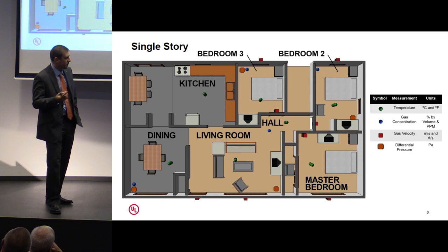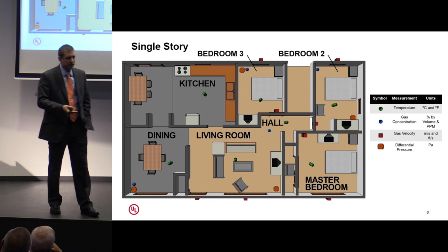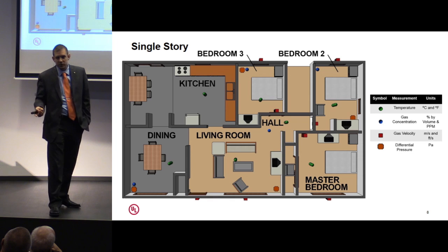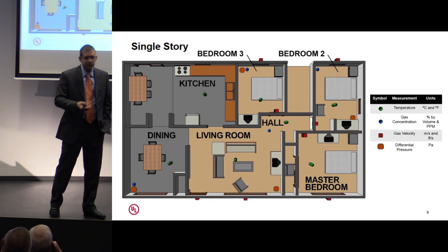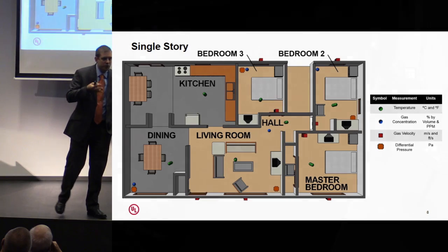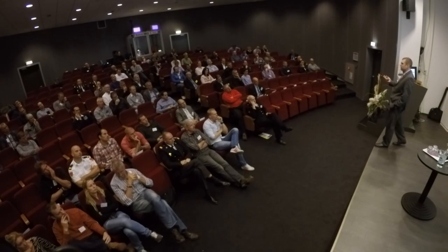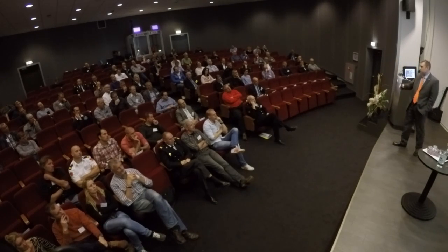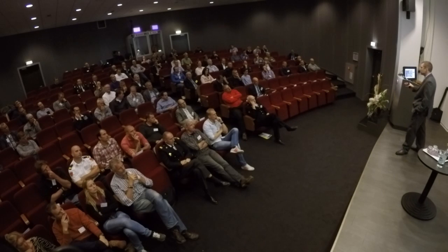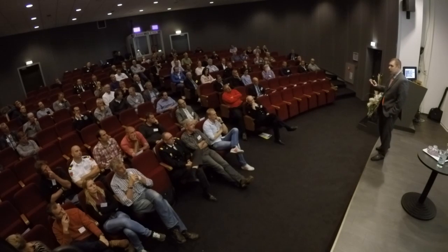And my thought on that is mainly because of how fire burns. If fire needs oxygen to burn, and all the oxygen's gone from the structure to the point where the fire can't burn anymore, does that mean people can still survive? And the answer is yes. If there's any fire safety engineers in the audience, you've heard of oxygen reduction systems that are designed to protect things like computer storage rooms or cold storage warehouses, where they take nitrogen and they pump it into the room to lower the percentage of oxygen down to roughly somewhere between 14 and 16%, which reduces the chance of ignition from fire, but it also reduces the ability of the fire to burn efficiently.